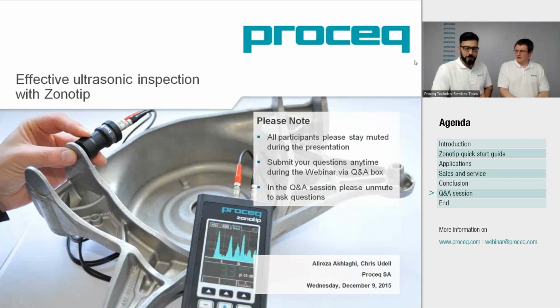One of the things that we're not supposed to be doing, but during the preparation of this webinar, we were testing our samples here, and it happened because we had several different units, and we disconnected the probe and did not zero and recalibrate, and we were confused why our results were not working. And that just shows the importance of zeroing and recalibration anytime you disconnect and reconnect a particular probe.